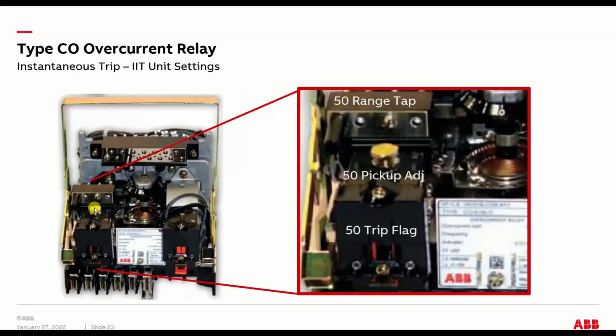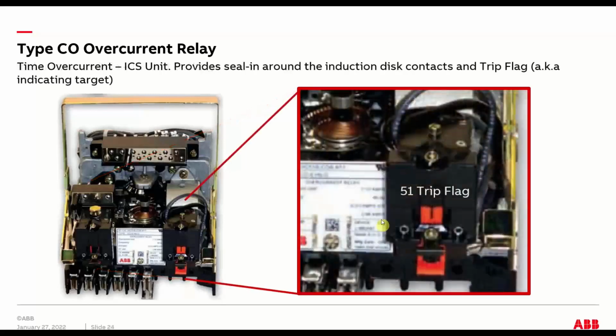This relay, the CO, also has instantaneous or 50 protection on it too. And that's just a separate element contained in the relay right here. Its settings are really simple too. You have a range tap, which is the same as the other tap. It's a screw that screws into whatever hole you pick. And then there's a pickup adjustment dial. That's all there is to it. And then this piece here would be a flag that drops if it picked up on that. But the point I'm getting across is that for an electromechanical overcurrent relay, you had a 51 tap, 51 time dial, and then 50 pickup with maybe a range. Sometimes there weren't even ranges on them, depending on the model.